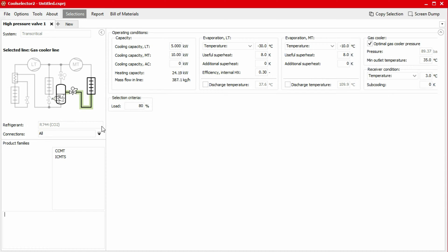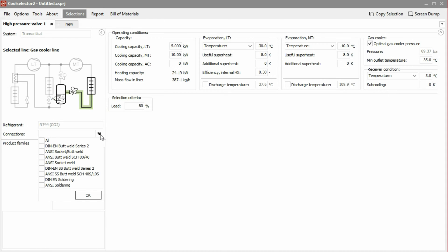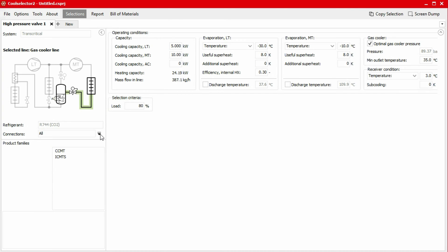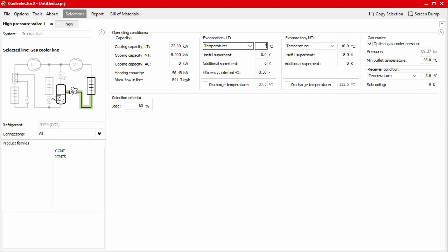The application has also defaulted to use the refrigerant CO2. We can choose the connection type we require, but for this example we'll leave this as all. We will now define the operating conditions at the top. We'll start with the cooling capacity. In this example, we'll input the low temperature cooling capacity at 25 kilowatts and then the medium temperature cooling capacity as 8 kilowatts. The low temperature evaporation temperature will be negative 32 degrees Celsius and the medium temperature evaporation temperature will be negative 10 degrees Celsius. We leave the superheat and internal heat exchanger efficiency as default.